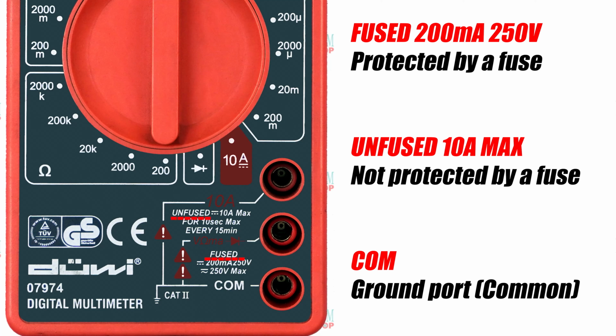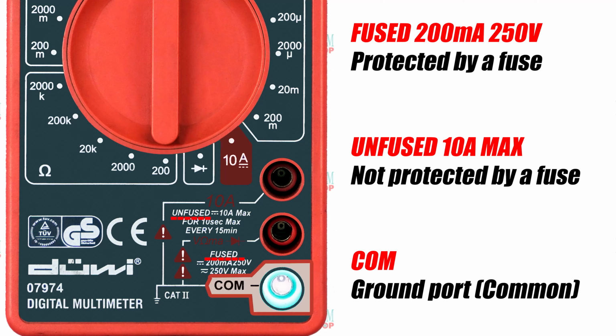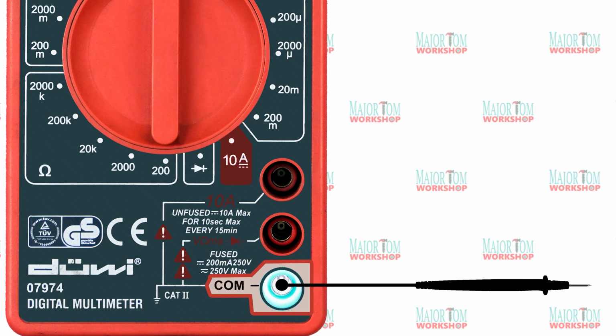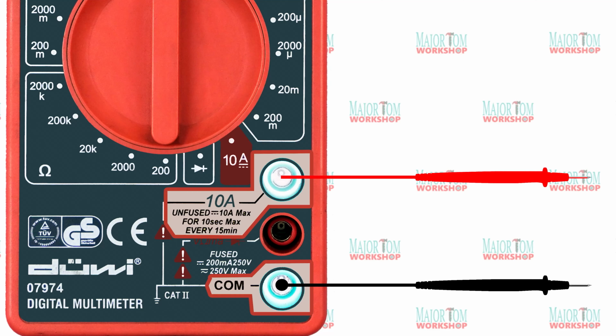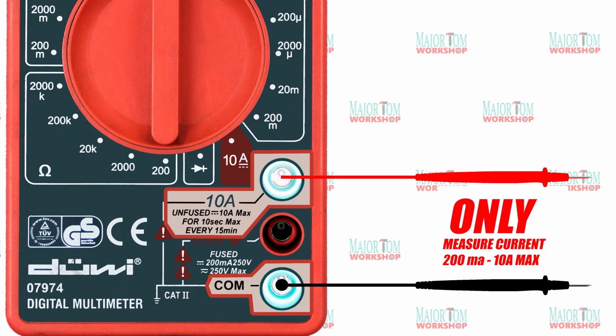Unfused obviously means the port is not fuse protected. COM means common. You must always connect the black probe to this port, and basically there's no reason to ever move it. The 10A port is used to measure current from 200 mA up to 10 ampere. The rest of the measurements are done with the remaining port.